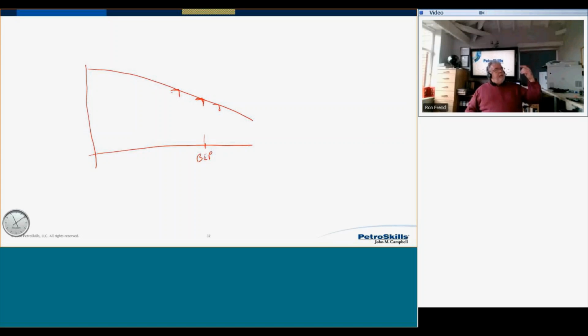So we take that in, say, yeah, okay, we've got 10%. And then you go to your boss, and your boss says, hey, yeah, that's a good idea, we need to add 10% more, which means you've got a bigger pump now, and you're operating even further down the range. And of course, by the time you get to purchasing, you could end up being way down here somewhere. And if your allowable range is like this, and this is your normal operating point, your sensitivity analysis could be over here somewhere. Which means that a lot of the time you're going to be operating way outside. You're going to be getting low flow cavitation, bearing failures, and a lot of seal failures.